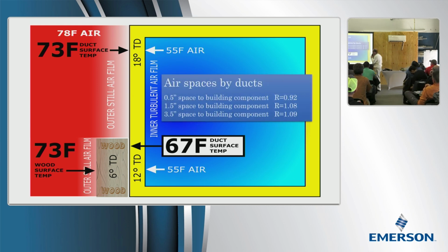And here's what you want to remember about that. Just a ½ inch of space is 1 R value. Now you remember how you had to drop your TD by 5 degrees just to get 1 degree. And if you spent the money and the labor to go from R6 to R8, which is substantial, you would only get 1 degree. You can get 1 degree just by not touching this. The R value of a ½ inch space between the duct and the building component is almost 1. And when you get into 1½ inches, it's R 1.08, so just figure it's about 1.